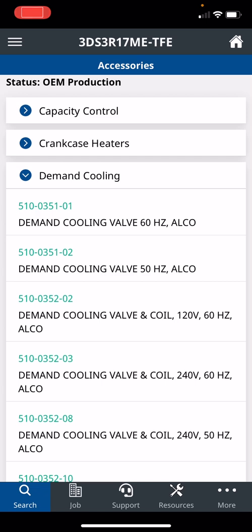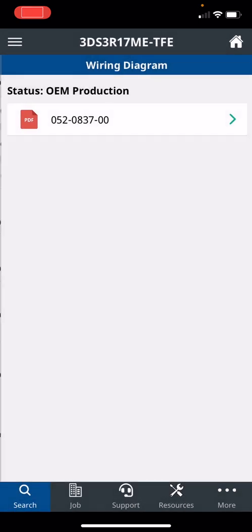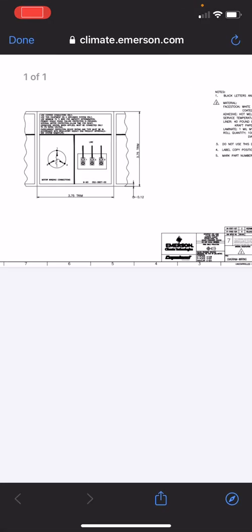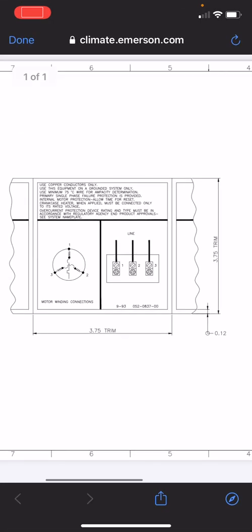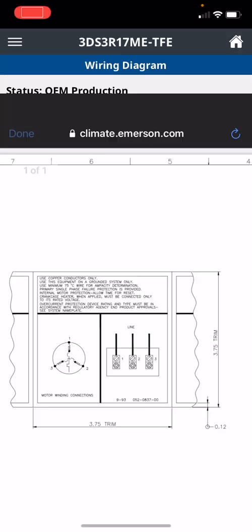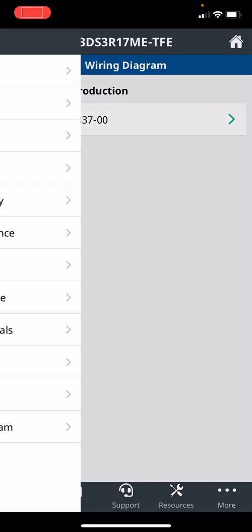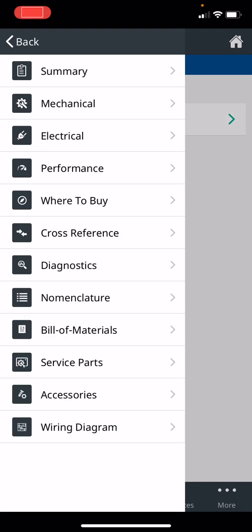And then you can go back and if it's a wiring diagram, this one's across the line so it's straightforward. But if you're doing a TSK compressor where there's nine leads, it'll show you how to do across the line, part winding start, where to put those jumpers. It's also on the back of the electrical plate. So that is really some of the main things.